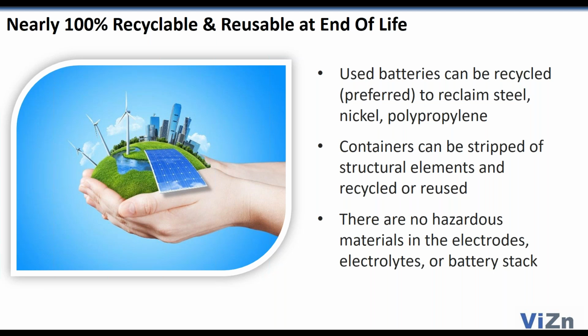The ViZn system, the electrolytes are designed to run at around 45 to 50 C. They can go up as high as 55 C. That's 125, 130 Fahrenheit. The system likes to be warm. It's very good for that reason in hot climates, and it does not need any HVAC. We actually have to keep it warm to keep our heating losses to a minimum. The system will self-heat when it's running. And we can use this in the worst of conditions.